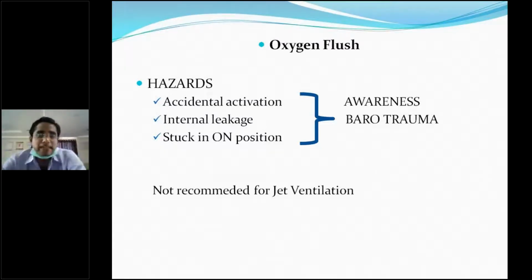That means he will be awake during surgery. And any internal leakage or sticking of this oxygen flush button delivers an excessive amount of oxygen to the patient, and this causes barotrauma. Hence, this oxygen flush mechanism is not recommended in jet ventilation.